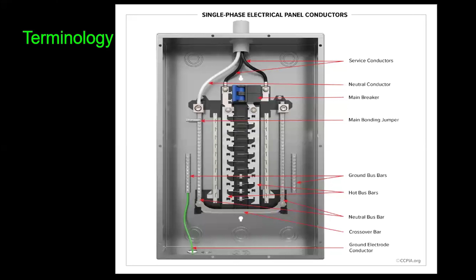We've used a lot more power these days. Your main bonding jumper connects the neutral and the ground, giving electricity another place to find its way home. That's why you have the ground there. Then you've got your bus bars that are hot on either side, connected to the main circuit breaker that will shut everything down when turned off. Then you have your neutral bus bars, crossover bars, and your grounding wire there.